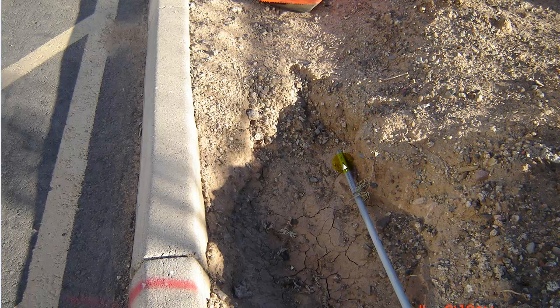Taking a look at it here from another angle, I think this might have been about 8 inches deep. We did have some rain and some of this floated up. When this trench was dug, if they had put dirt over the top of it every five feet or so, it would have kept that pipe from floating. Nonetheless, it got turned down by the inspector.